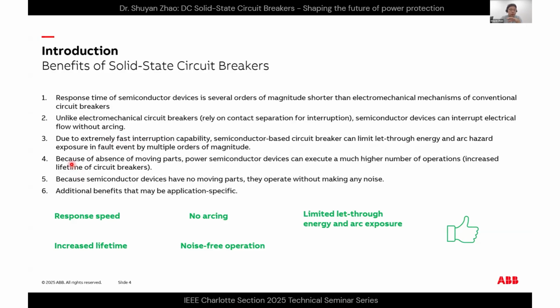Because of the absence of moving parts, meaning no contact separation, power semiconductor devices can execute a much higher number of operations, increasing the lifetime of circuit breakers. And because there are no moving parts, they also operate without making any noise, unlike metal contacts which always come with a big noise.